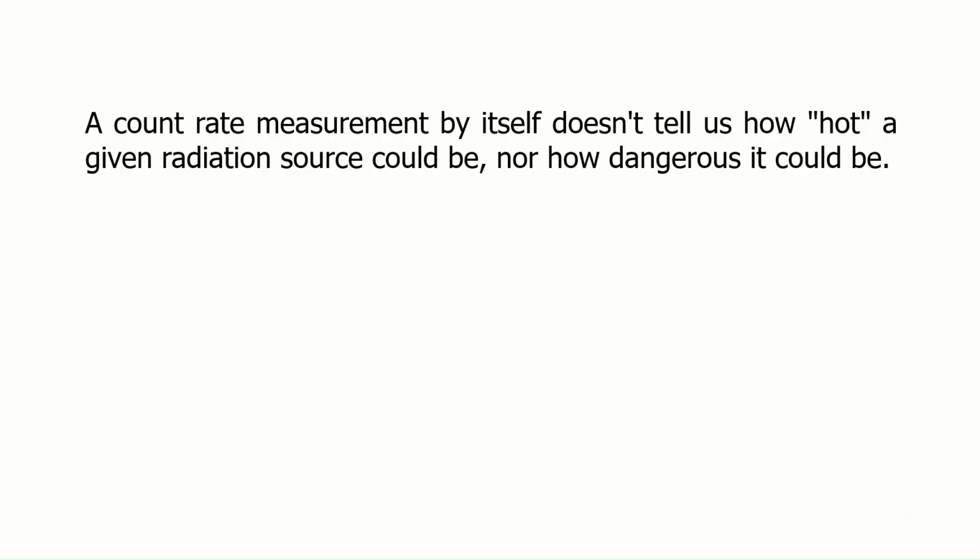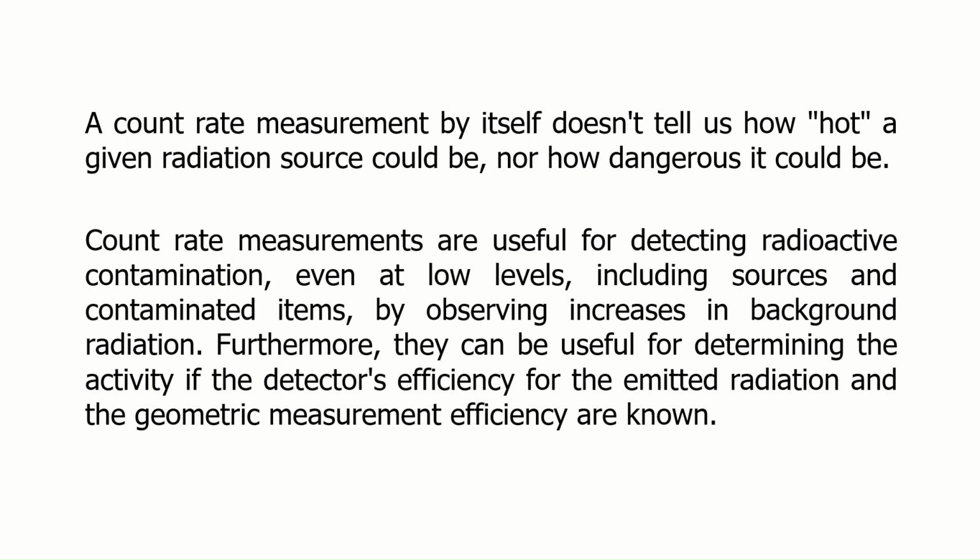A count rate measurement by itself doesn't tell us how hot a given radiation source could be, nor how dangerous it could be. Count rate measurements are useful for detecting radioactive contamination, even at low levels, including sources and contaminated items, by observing increases in background radiation. Furthermore, they can be useful for determining the activity if the detector's efficiency for the emitted radiation and the geometric measurement efficiency are known.